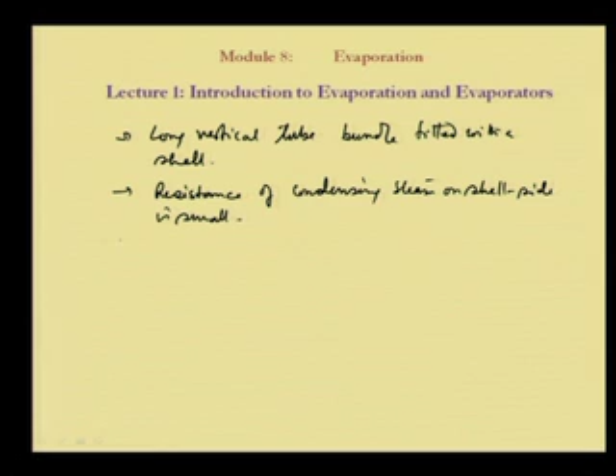Now, an important point is that the resistance of condensing steam on the shell side is always small, that is always true. But in the case of the long tube, the heat transfer coefficient is initially less and then increases due to boiling. Once the boiling starts, turbulence starts, so the heat transfer coefficient increases.